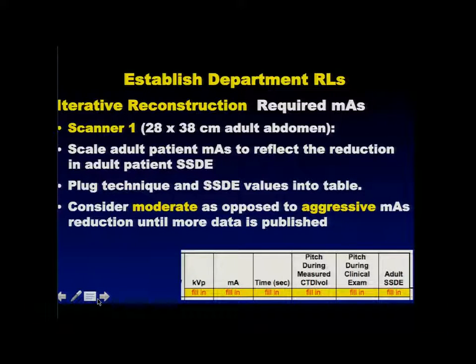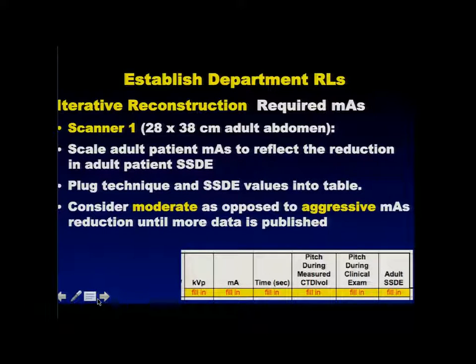Most sites today are using iterative reconstruction. Everything discussed so far assumes no iterative reconstruction. To apply this to iterative reconstruction: most sites pick a moderate level of iterative reconstruction through trial and error and settle on a clinical level. All you need to do is calculate what the CTDI vol would be at the iterative reconstruction techniques instead of standard techniques, then plug that data into the colored boxes in the tables. The ImageGently tables work for iterative reconstruction too.